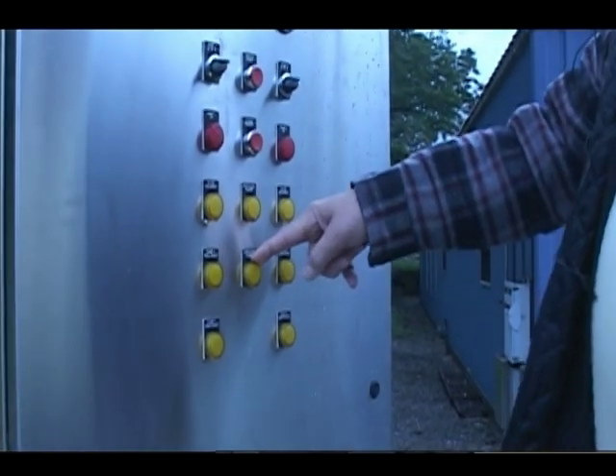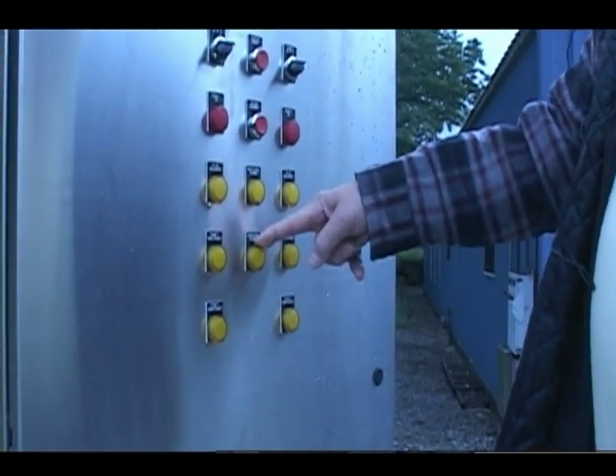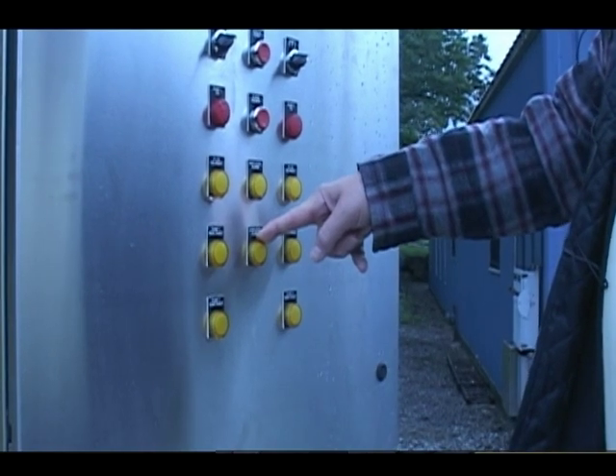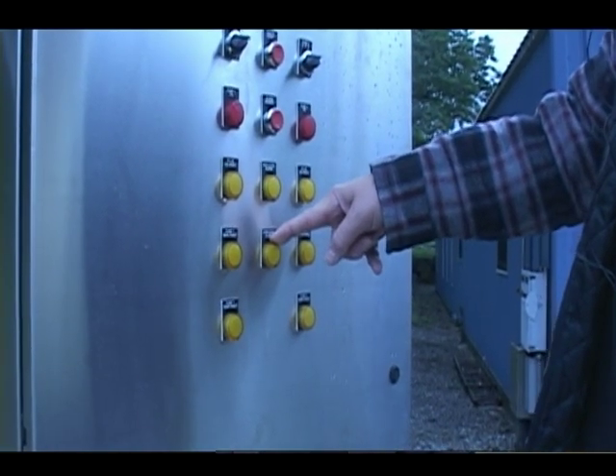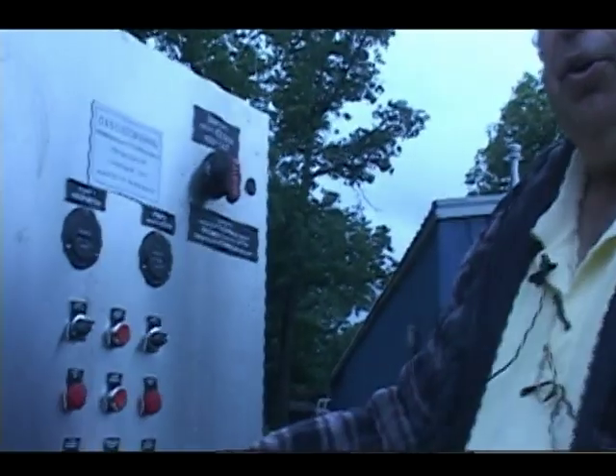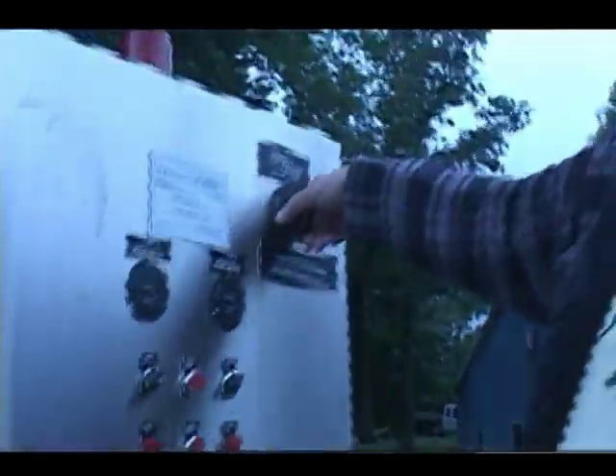The low level fault says that in the automatic mode the pump stayed on too long and continued to run when the pump off float should have shut it off. You'll have to see why it continued to run. Right? Now we're going to open the door and show you the inside of the panel.